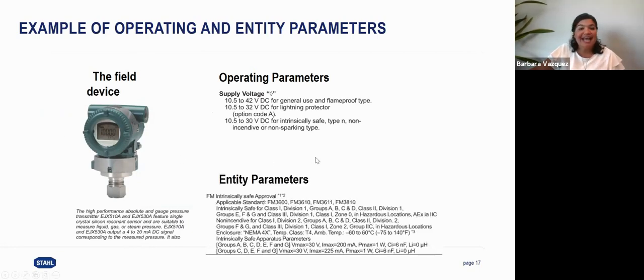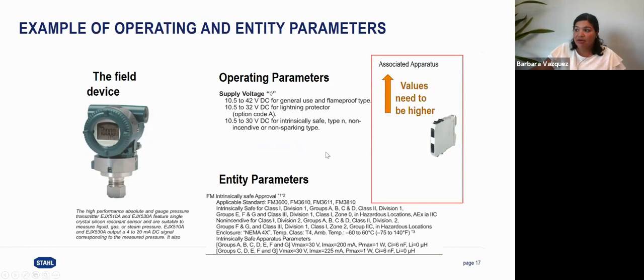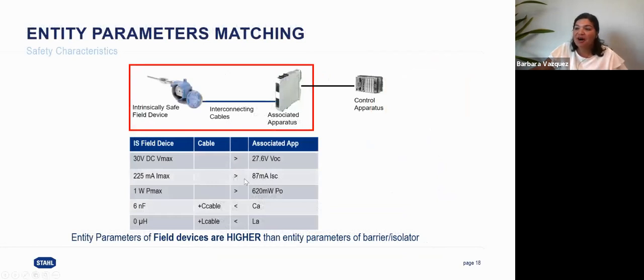On the same data sheet, we see the entity parameters. The entity parameters are the intrinsic safety data. Here, we can see the intrinsically safe apparatus parameters. For example, we're going to use groups C, D, E, F, and G. We have 30 volts, 225 milliamps, 1 watt, 6 nanofarad, and 0 microhenries. So this is the safety data, and this is the operating data. Our associated apparatus needs to be able to energize this field device and make it work, so it needs to provide at least 10.5 volts and at least 20 milliamps. But for the safety data, it needs to provide less than the safety data of the field device. So let's check this in a table. I like it better that way. On my table, every intrinsically safe device will have a set of entity parameters.